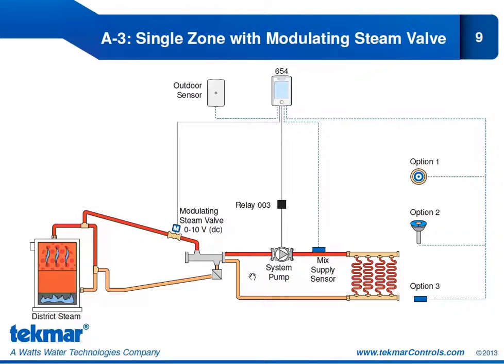We are also operating a system pump, and remember, because our auxiliary contact is connected to the R, we do need to use the isolation relay 003 to operate that system pump. Again, we have our 3 sensor options. We have the 090 or 094 automatic snow ice sensor, and that will give us the automatic start and stop. We have option 2, which is the snow sensor 095. And using this option would give us automatic start and time stop.